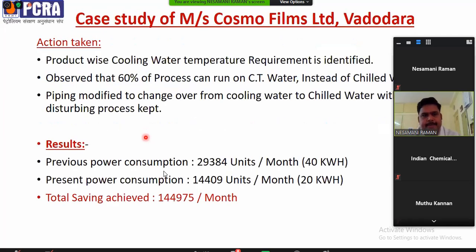So what is the solution? The solution is the case study of Cosmo Films Limited, Vadodara. They analyzed and identified the cooling tower temperature requirement product-wise. They observed that almost 60% of their process can run on cooling tower temperature water instead of chilled water, since at higher temperature they can run, and that was not a problem. So they modified a pipe so that if they need a particular temperature, they can combine both waters so that the process is not disturbed.